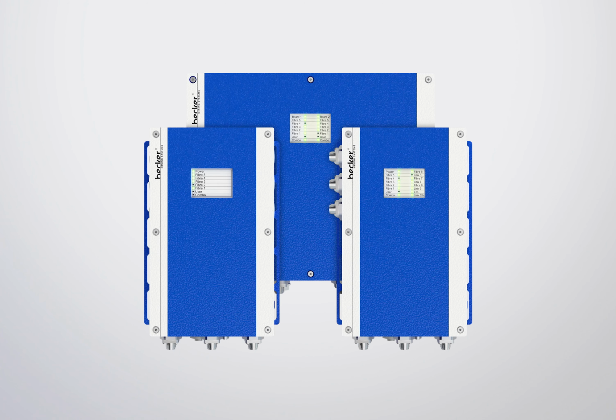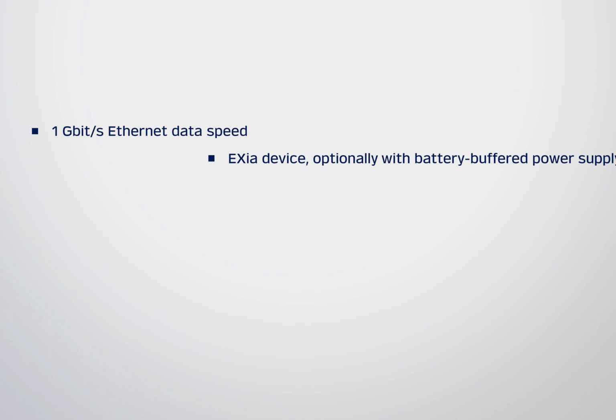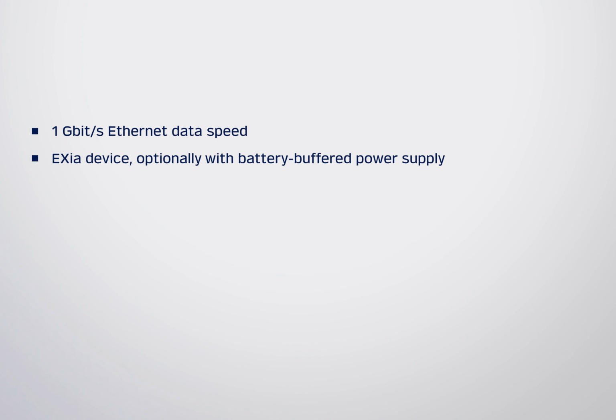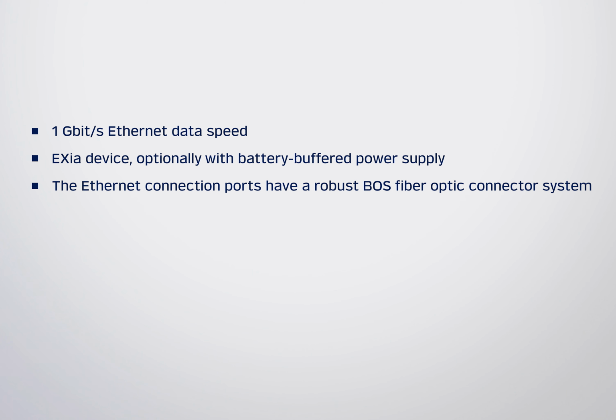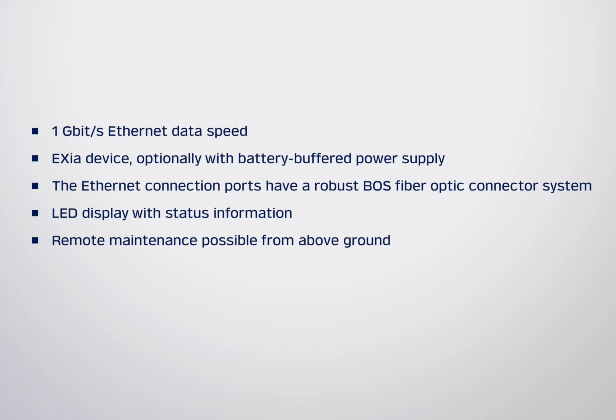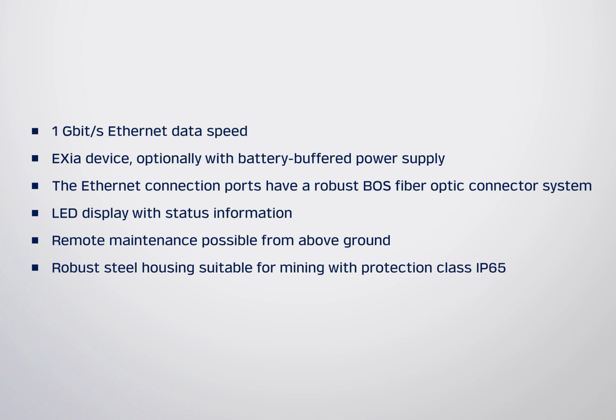The devices exhibited here are intrinsically safe Wi-Fi routers and Ethernet TCP/IP switches from the RAP260 product range. The devices are available as Wi-Fi routers or Ethernet. The RAP260 devices have a number of technological highlights such as 1 Gbit per second Ethernet data speed, EXia device, optionally with battery buffered power supply. The Ethernet connection ports have a robust BOS fiber optic connector system, LED display with status information, remote maintenance possible from above ground, robust steel housing suitable for mining with protection class IP65.